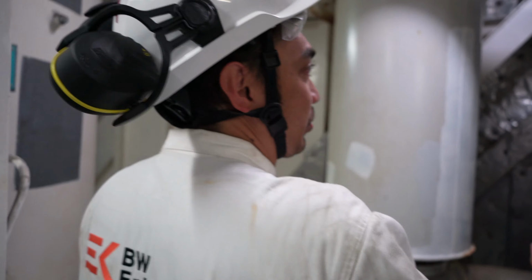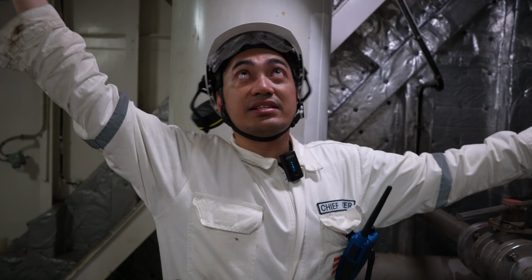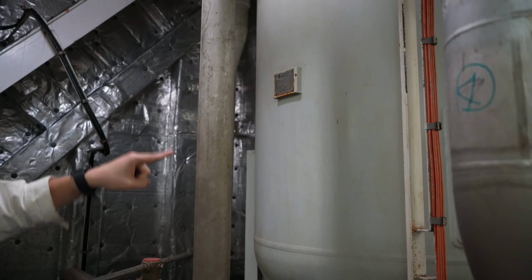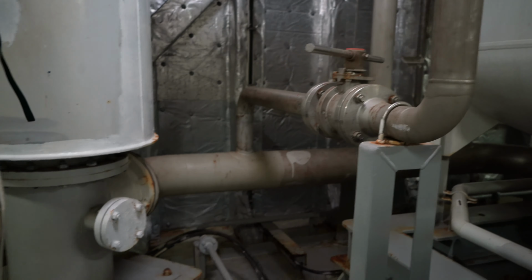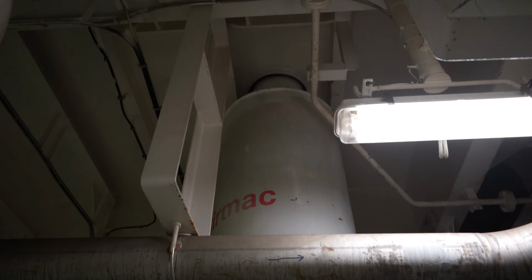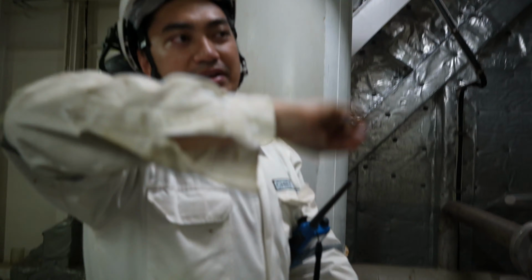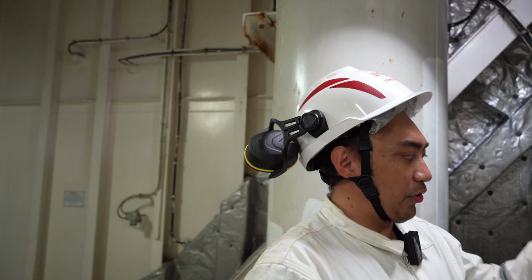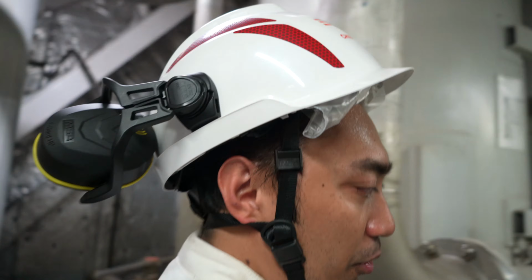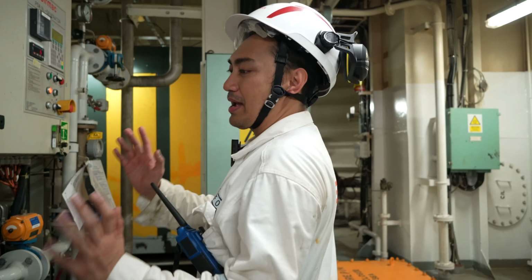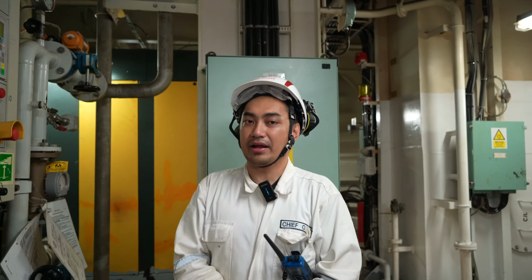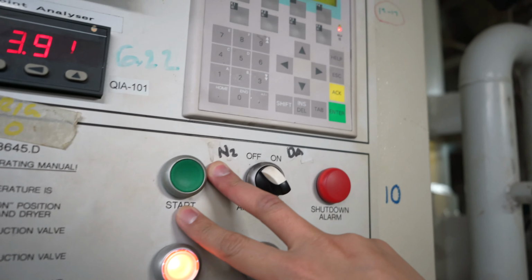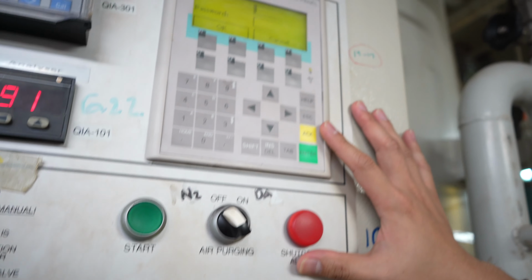With this bypass valve, from the supply you have an option to direct it to the PSA, and another one here, which goes directly into the atmosphere. So bleed everything to the atmosphere until you are certain that the dew point is lower, before you shut it, and then we can operate the PSA. When we have met the 6 degree criteria, the start button will flicker, and when that flickers, acknowledge all alarms first.